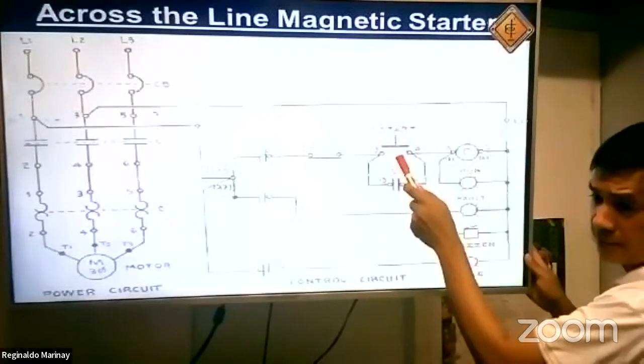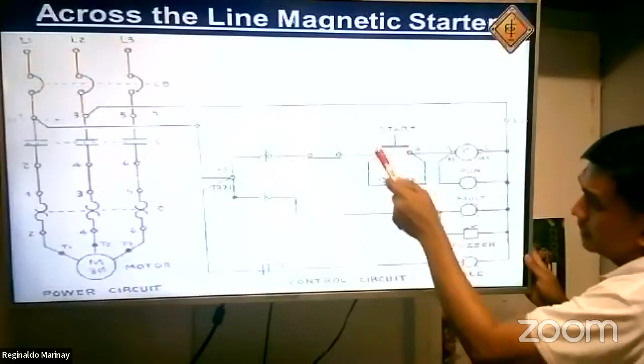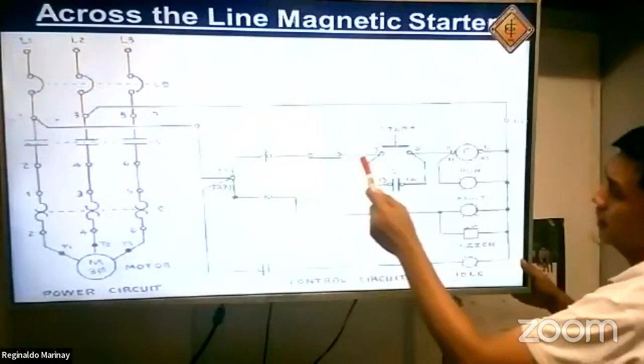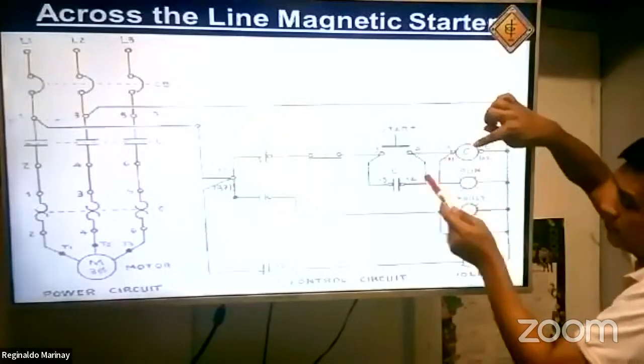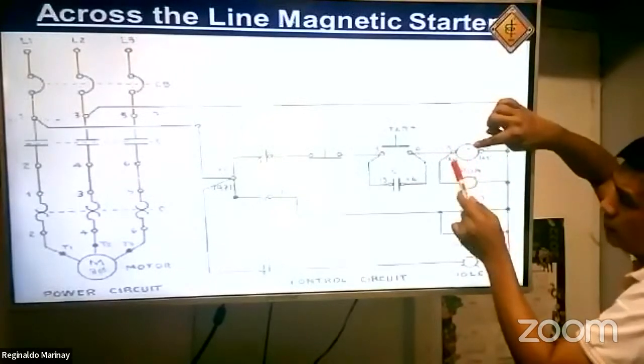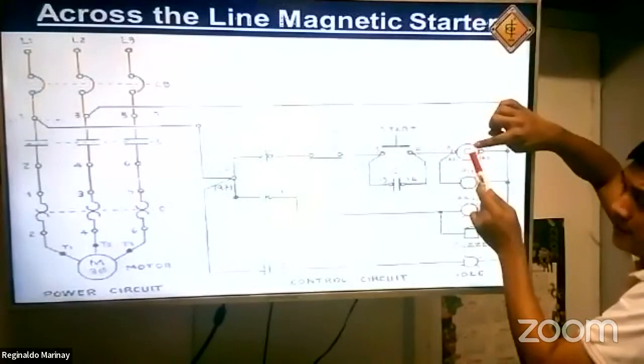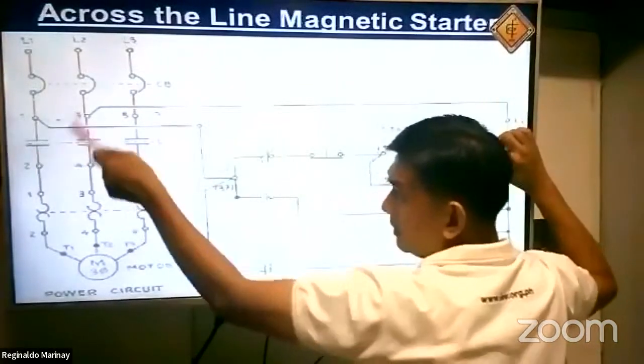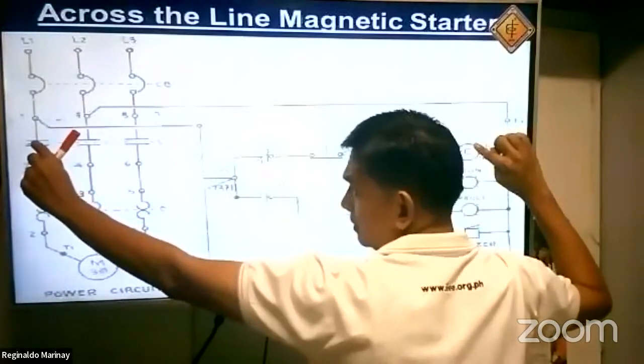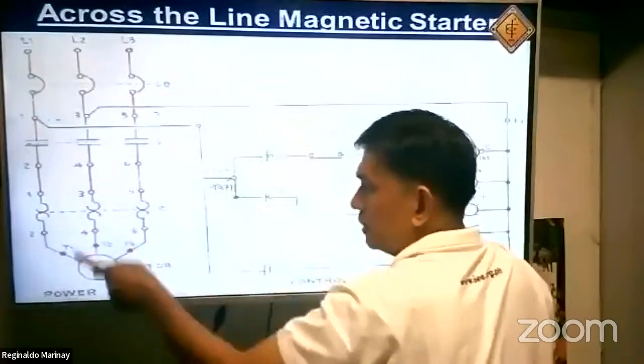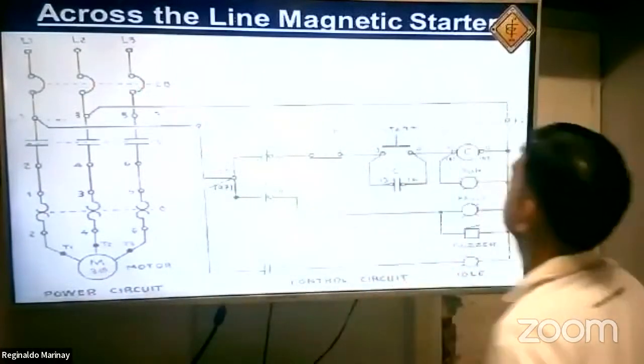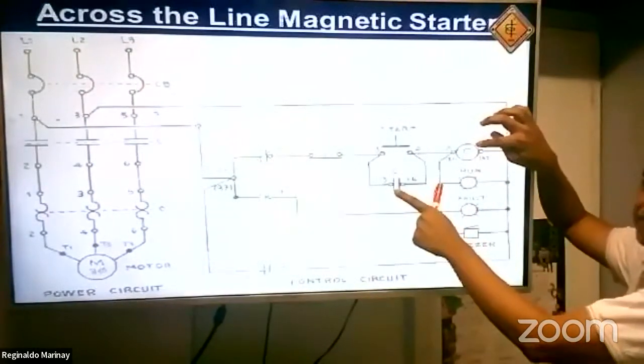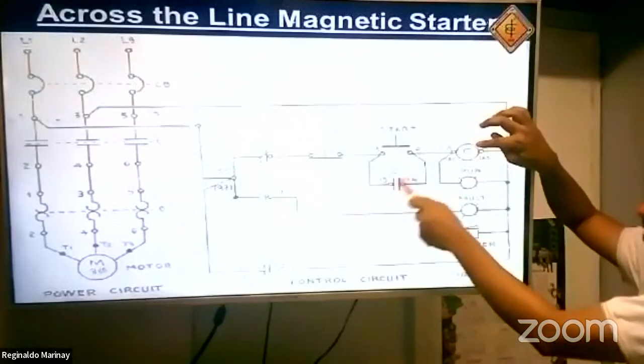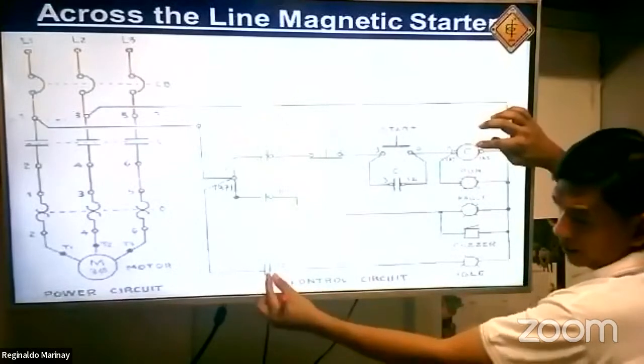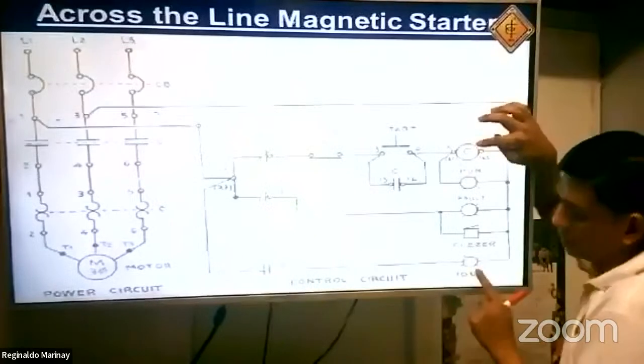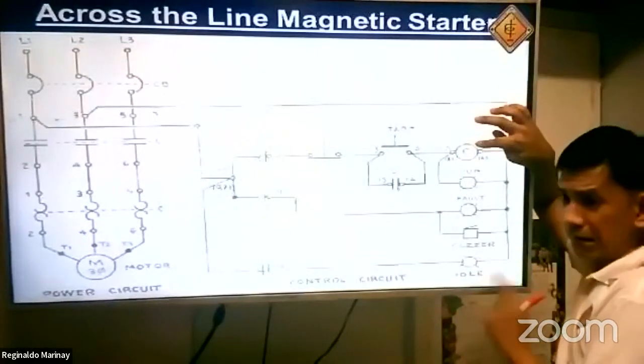Now, let us go here with the start button. I will press this push button. This is normally open. This becomes closed. The current will flow from line 1, energizing your holding coil C and your run lamp, of course, because they are connected in parallel, right? Energizing your holding coil C simply means that these 3 contacts, 1, 2, 3, 4, 5, 6, all at the same time, simultaneously, will become closed. Sabay-sabay yun. Energizing your motor, right? Your motor will become energized. At the same time, this latching contact, 13 and 14, will become closed. At the same time, this 11 and 12 will become open, de-energizing your idle lamp. And the one running is the run lamp already.